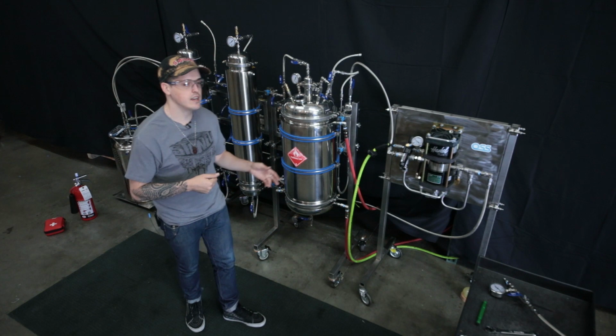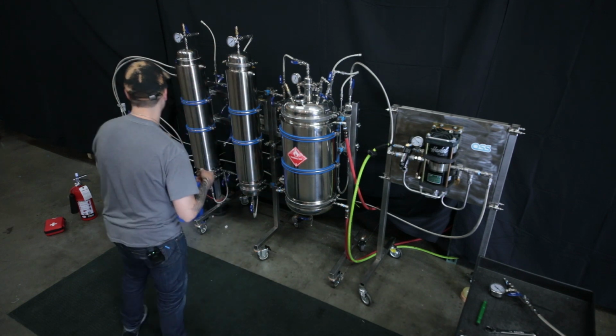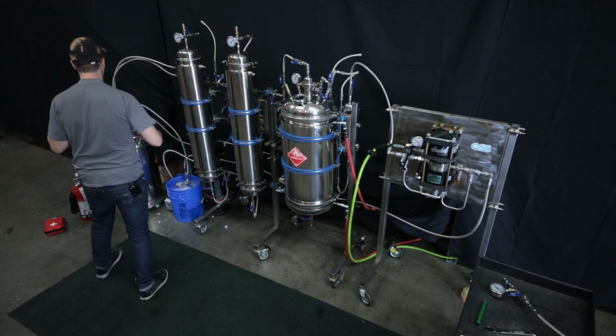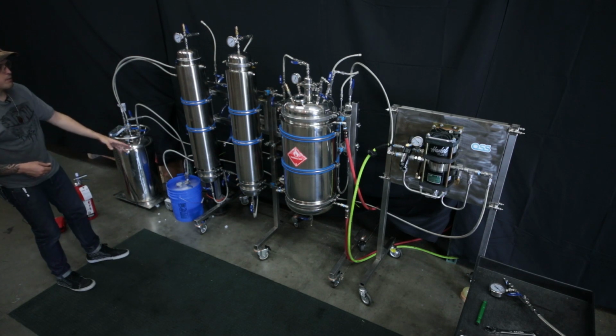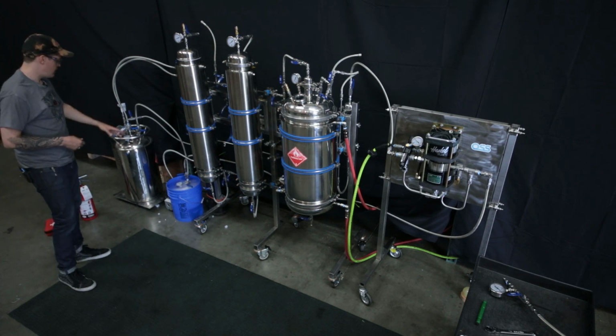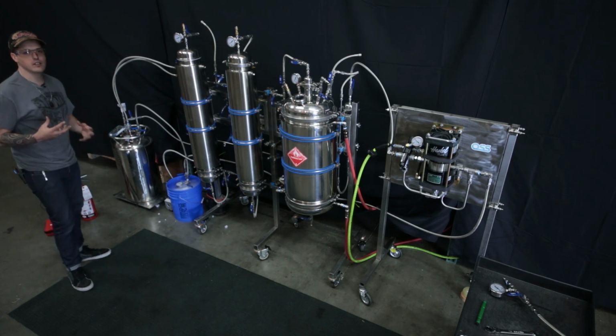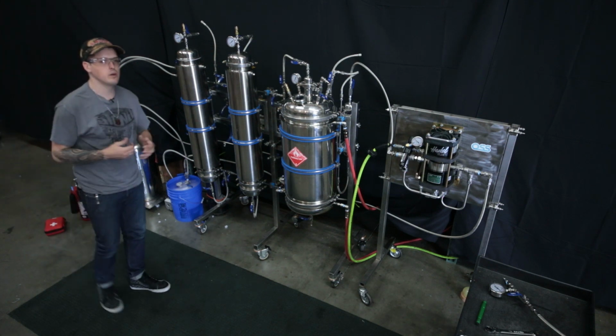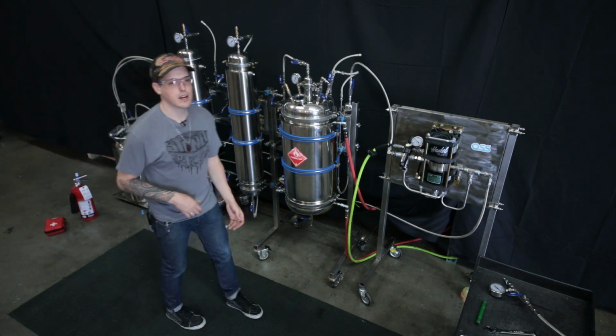The 120 degree Fahrenheit evaporation chamber feeds through that pump, and the pump also generates some heat. That heat needs to be cooled down before it goes back into the tank, so we don't build up back pressure and make it difficult to recover the gas. It'll condense all those hot vapors back into a liquid, which we can put right back into our storage tank.